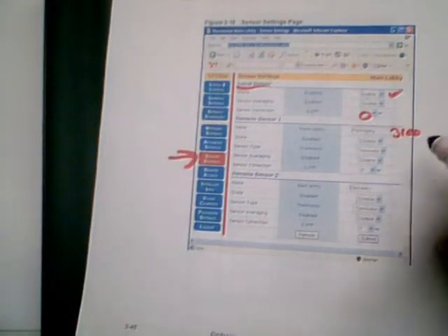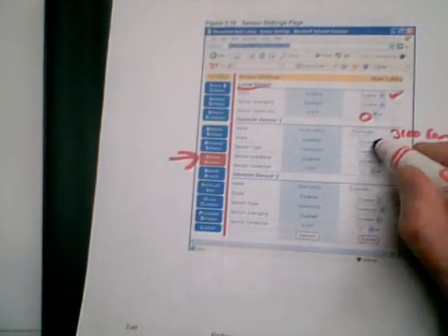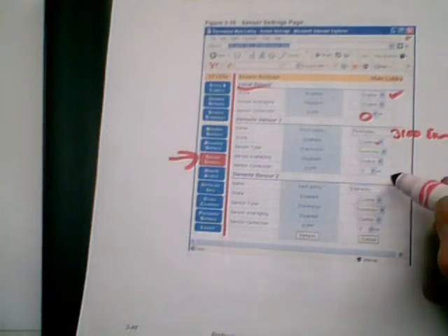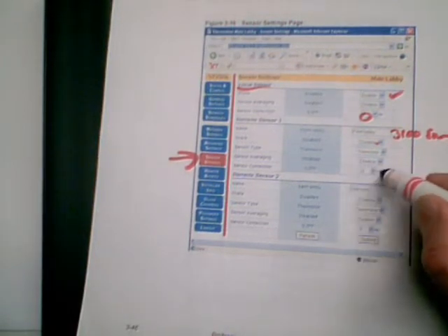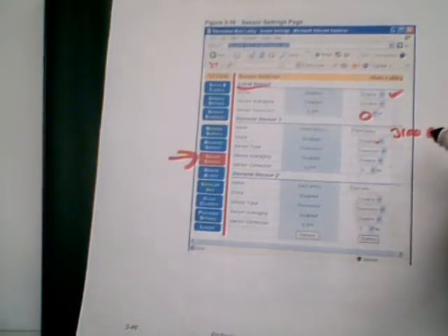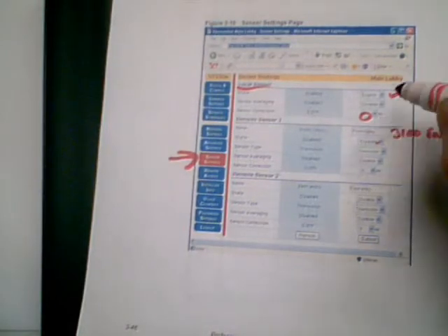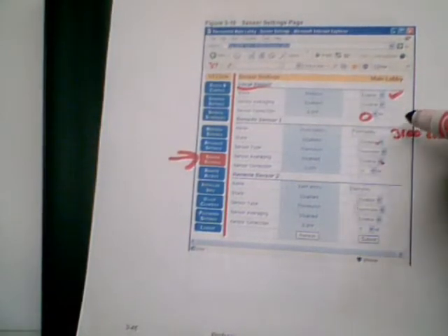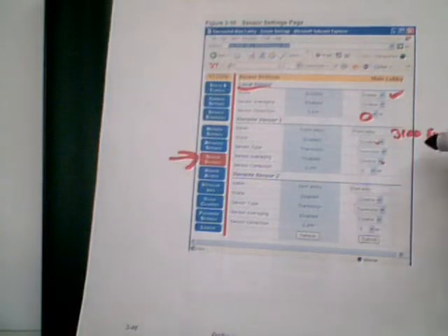So we'd say a 31st Street entrance, and of course enable it, and then again you have sensor correction on that, and then what you would normally do is average. You'd say click this down and say enable, and then enable this one, and it would average these two and use that for the control point of the thermostat in terms of if it turns heat on or off.